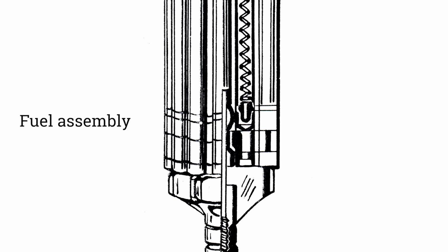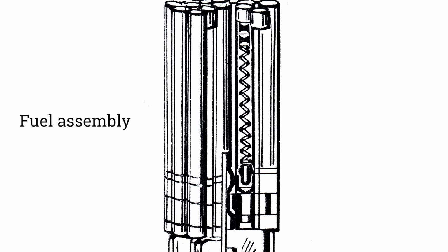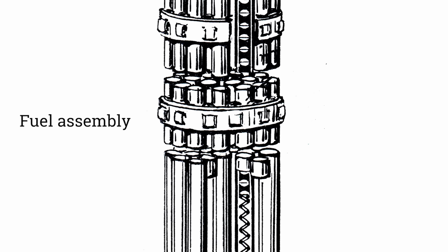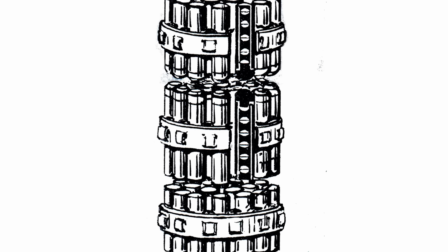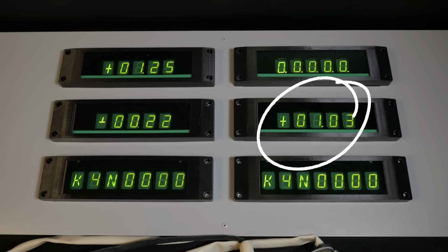If channel power rises, more steam is produced. And if conditions become too severe, separate steam bubbles begin to merge in a continuous layer around the fuel element surfaces, and that is a big problem. That's because steam transfers heat far less effectively than liquid water. And basically, once this insulating layer forms, the water can no longer remove enough heat. That can make fuel temperature rise extremely quickly, and fuel can just melt. So this number therefore tells the operator how much margin remains before such a condition may begin. The value must remain greater than 1.